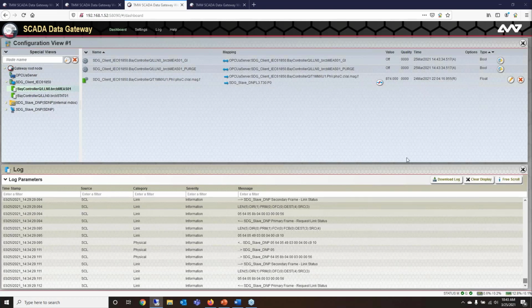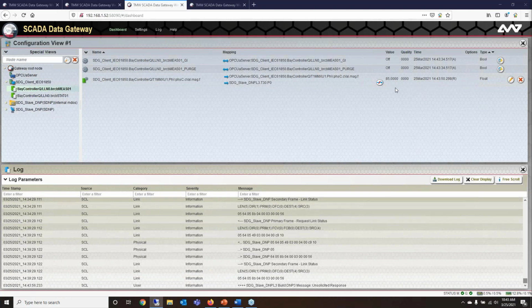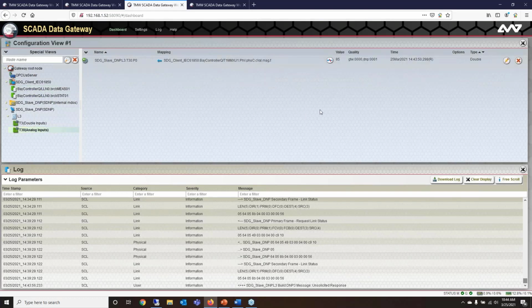And what we'll see is that this value should come along a lot faster. We don't have to wait that 15 seconds or 5 seconds for it to come across, because as soon as I changed it within DTM, it went ahead and published, or pushed, that report out to our 61850 client. And of course, like before, that value is also carried over because of the mapping to our analog value here, and reported up to the control station in my DTM as well.